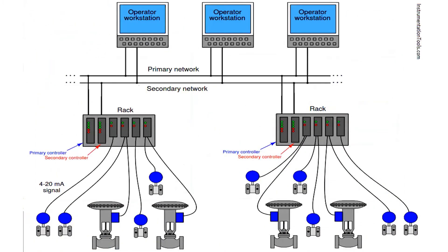This is a representation of a basic DCS with operator workstations, a network, and a rack with PLCs. The controllers take sensor data from sensors and control valves. Importantly, there is a primary and a secondary controller — in many DCS systems you build in redundancy for resilience, because downtime is very costly. This is achieved through dual networks, dual controllers, and so on.